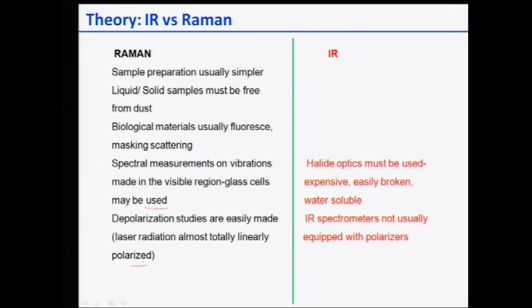The laser radiation is almost totally linearly polarized, but in the case of IR, halide optics must be used. As you have seen, they are very expensive, can be broken, and can also absorb water, because basically other than halides, most of the materials absorb the IR radiation, and it is not possible to get good data. IR spectrometers are not usually equipped with polarizers. On the other hand, Raman spectrometers are usually equipped with polarizers.